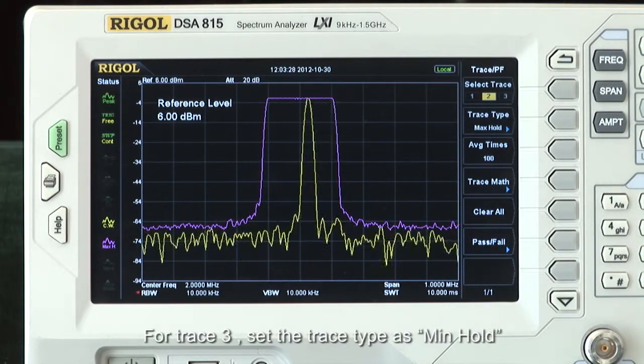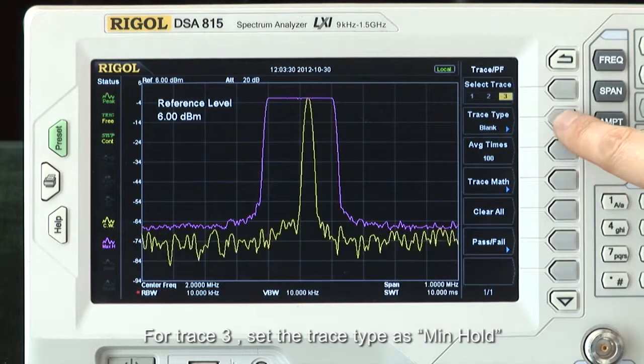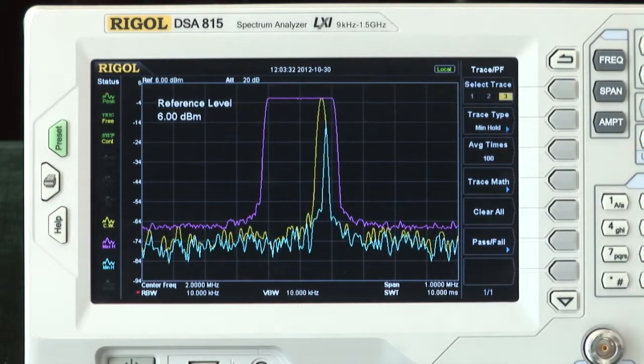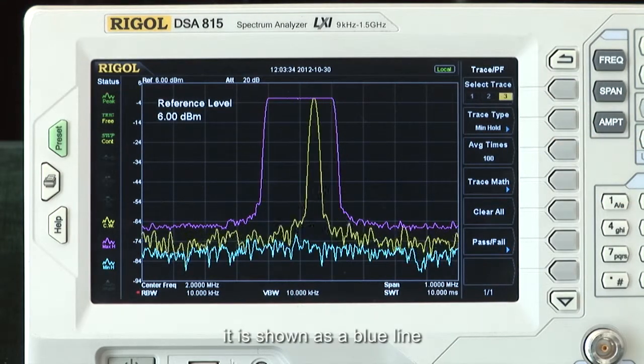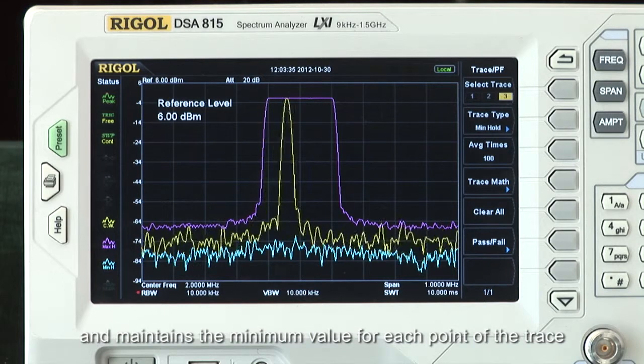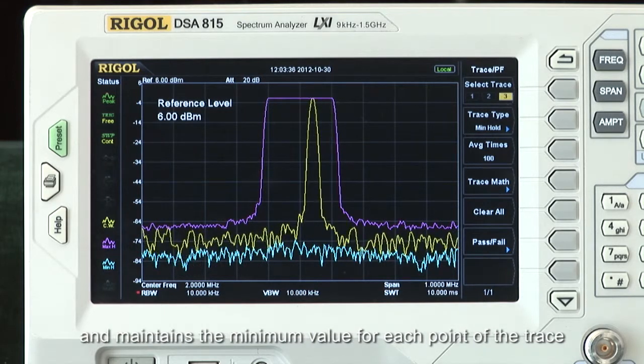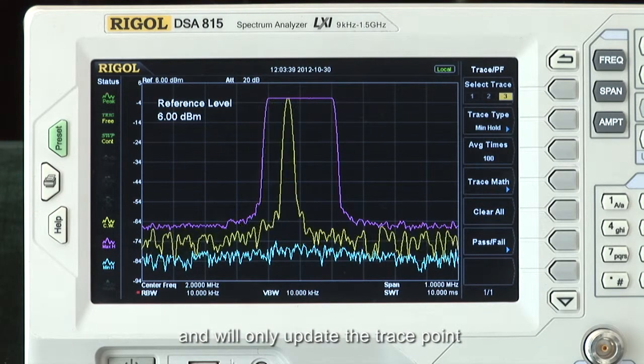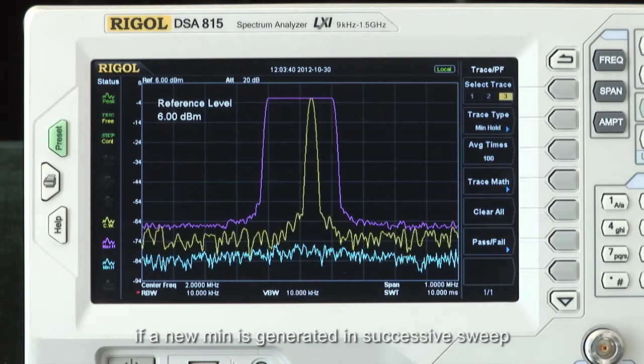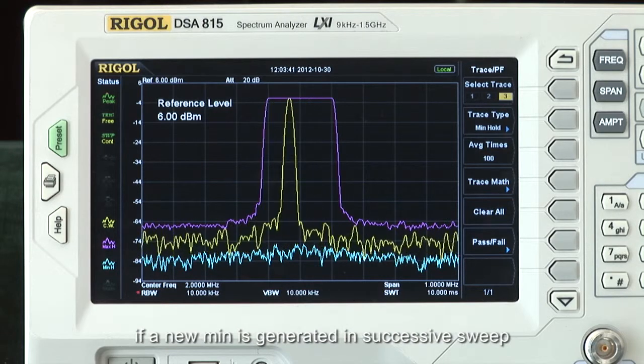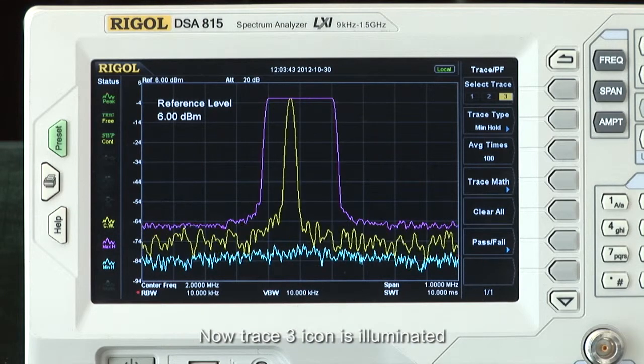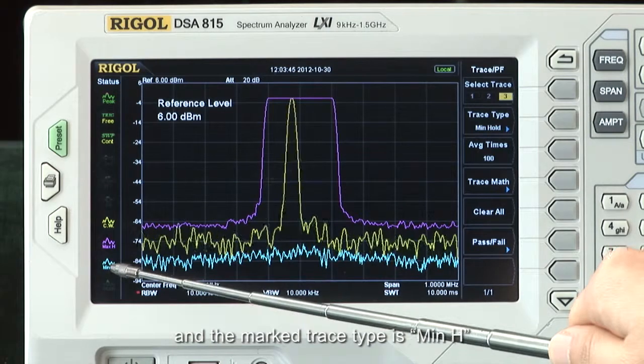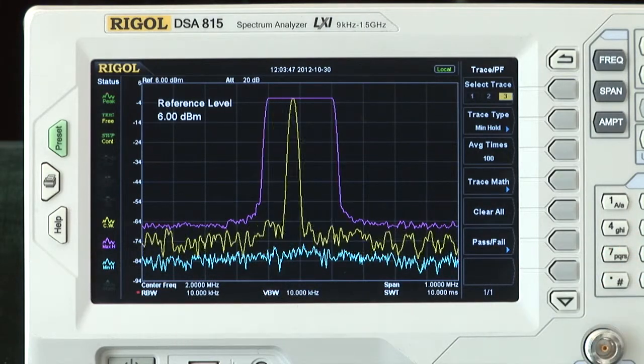For trace 3, set the trace type to min hold. It is shown as a blue line, and maintains the minimum value for each point of the trace, and will only update the trace point if a new minimum is generated in a successive sweep. Now the trace 3 icon is illuminated, and the marked trace type is min H.